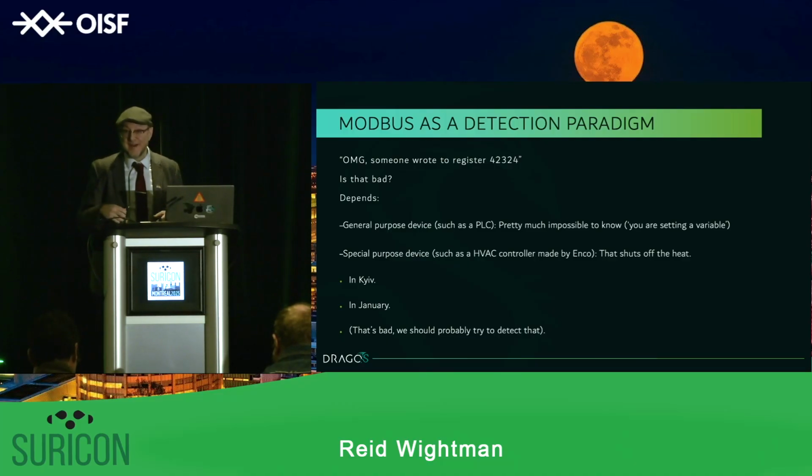And there are a lot of systems out there that will take that heartbeat message and will treat it as, okay, I'm in remote operation mode. That means there's an operator at a workstation that's going to click around and make changes and adjustments to me. And if I don't see that heartbeat for a while, then I'm going to go into local control mode. I'm going to assume there's no operator at the helm. I'm going to go into my default operating state.